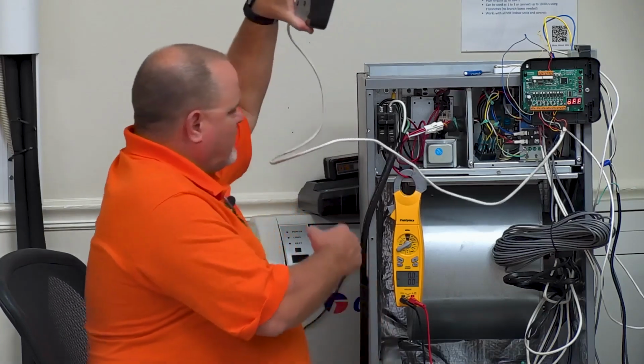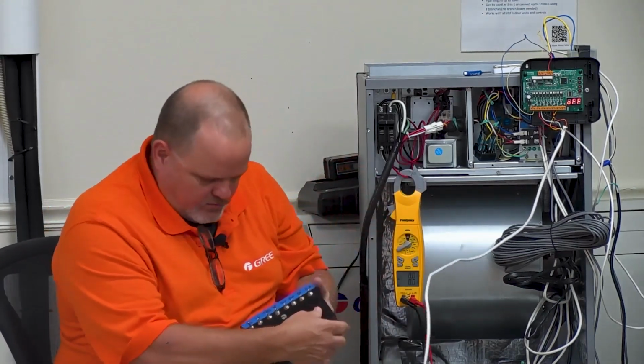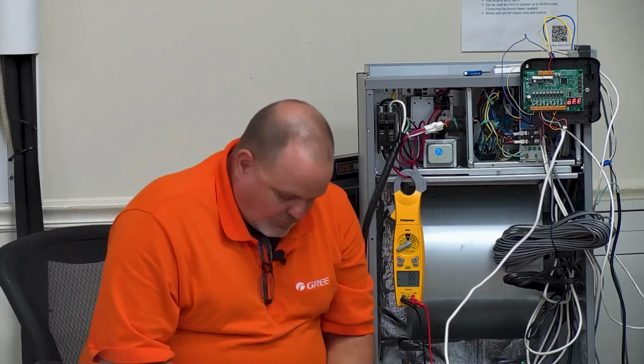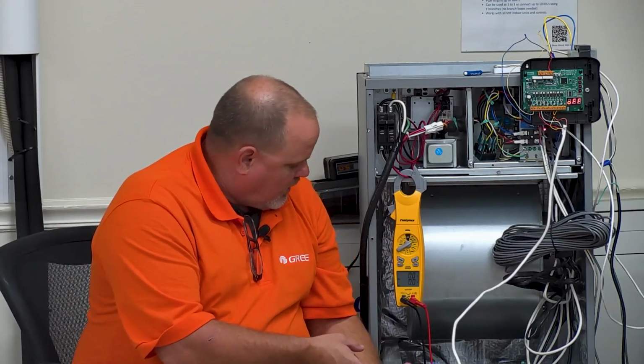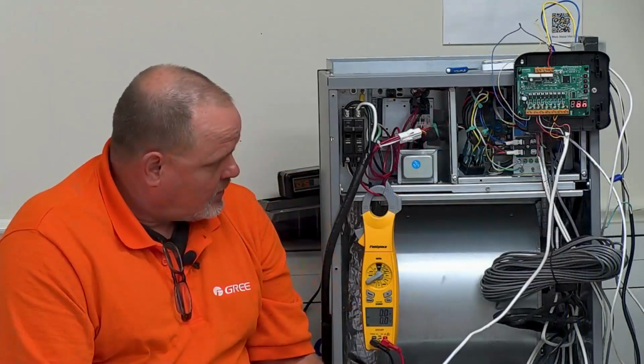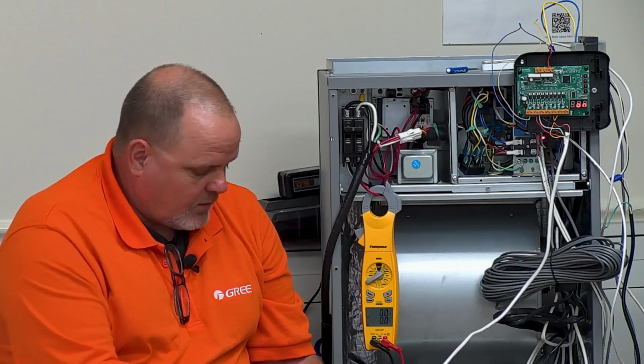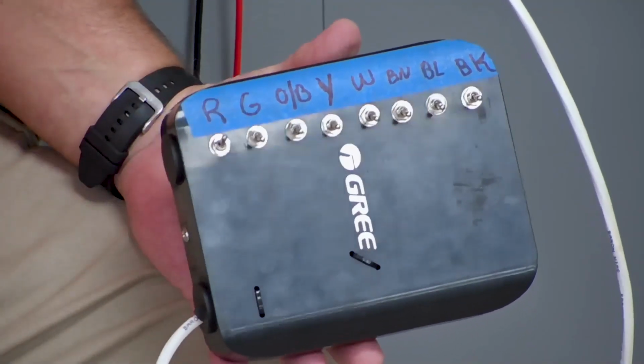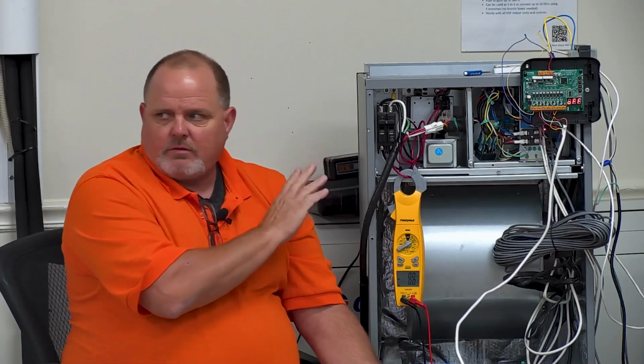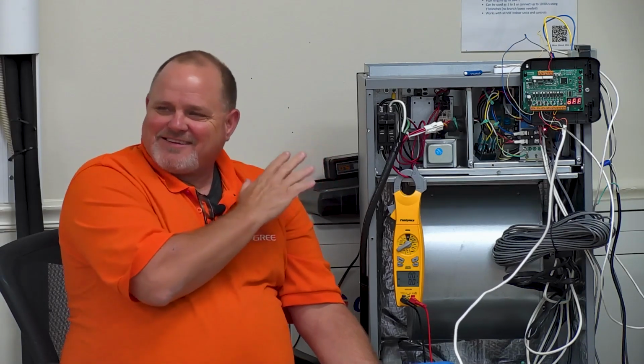I got my own homemade zebra stat here. So if we give this a fan on call, I'll turn on the fan. You can see the 24-volt adapter went to on. So we'll give that a second. So fan's up and running. Lose the fan call. And I set that to where, in this, again, this is a prototype, so those timer off settings are not correct in here. So I had to play with it.